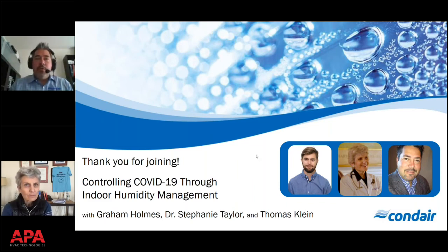as long as we, so two parts. A, something like the DL or hybrid, it's got a hygiene certificate. We're being very cautious about the water. So its water passes through a UV light first before we introduce it into that system. Secondly, we're introducing a small amount of silver ion to that. So in that case, there's absolutely no chance of microbial growth or anything that you're going to be worried about. So the cost is typically a silver canister that lasts a year and a half to 2 years, typically. That's just part of the system, and we would show that to you. We're upfront about what it costs and when it needs to be taken care of.